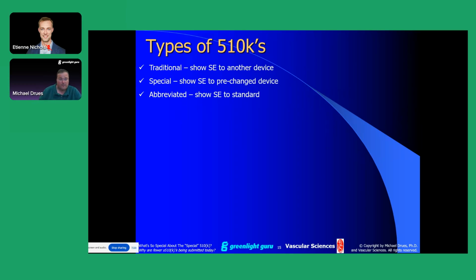And one quick comment about the abbreviated 510K: the word abbreviated is very deceptive. Abbreviated doesn't mean shorter or faster. In fact, the refuse to accept or the RTA guidance for the abbreviated 510K is many pages longer than for the traditional 510K. Let me say that one more time. The RTA guidance for the abbreviated 510K is significantly longer than for the traditional 510K. So abbreviated doesn't necessarily mean what you think it is. Kind of to quote a famous politician, kind of depends on what your definition of is.